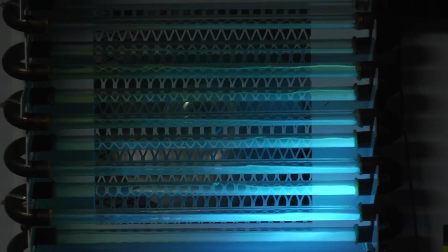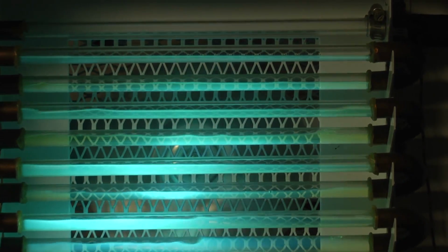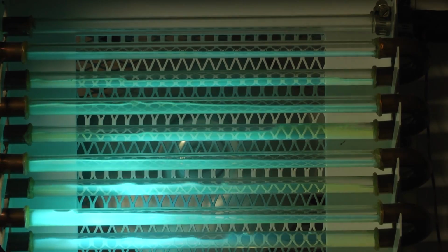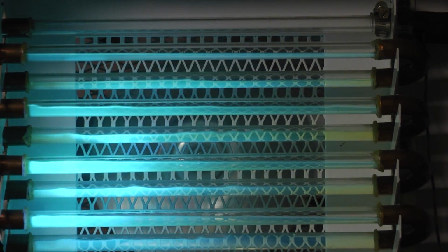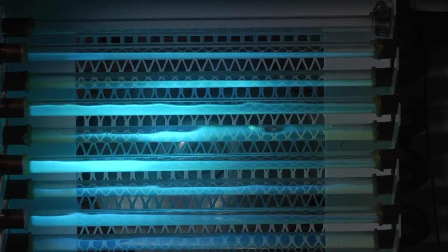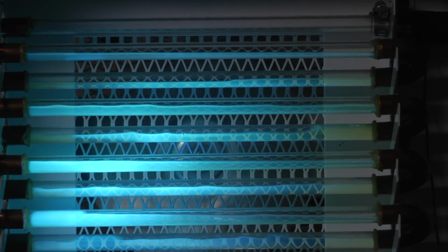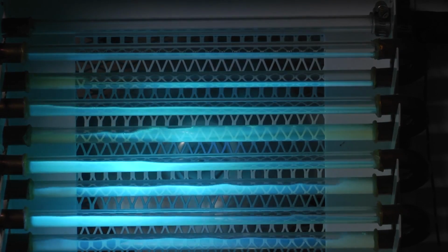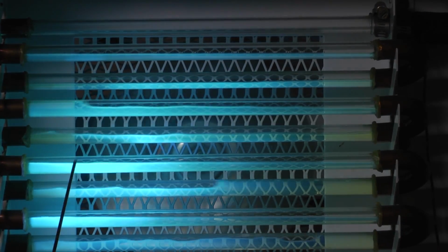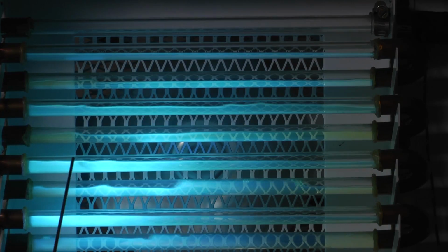As you look at our first tube here, you can see that about 20% of the refrigerant has transferred to vapor already. Now, the liquid refrigerant is going to continue to travel through our evaporator coil where the refrigerant is absorbing heat from the conditioned space. As it does, the heat that enters the refrigerant changes the state of the refrigerant. It continues to boil the refrigerant or evaporate it in the evaporator coil. You can see in the center here, there's less liquid and there's more vapor.